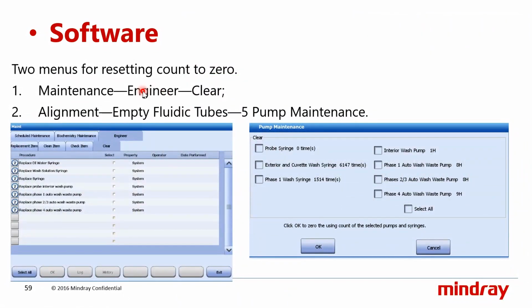There are 2 menus for resetting the count to 0. Whenever you are replacing any pumps or syringes, you have to reset it. We have two menus. Suppose you change the syringe, it will already show some cycles completed. Whenever you are replacing it, you can reset the syringe to 0. So you have the option in the maintenance engineer. Here you can clear it. You can select that particular one, select all and okay, then it will get 0.